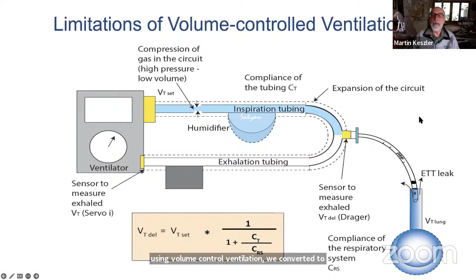And there will always be a loss of volume to compression within the tubing and humidifier, some stretching of the circuit. But when there's a large patient with large lungs attached here, this is not a real problem, and it can be compensated by an algorithm, the compliance compensation algorithm. However, when you attach a very small baby over here, less than a kilo, who is intubated with an uncuffed endotracheal tube with variable leak around the tube, this system breaks down and accurate tidal volume measurement is not possible. And that's why many years ago, when some of us were starting in the field and tried using volume control ventilation, we converted to pressure limited ventilation as the standard modality.